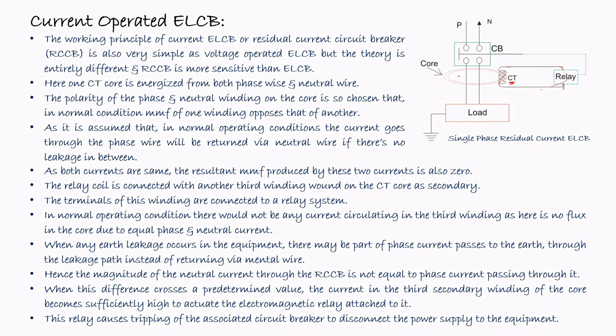But during some leakage, earth leakage, the current through the phase and neutral will not be equal. Therefore, the CT coil will be activated, it will be energized, and it will give the information to the relay. The relay will be activated and it will trip the circuit breaker which is connected with this relay.